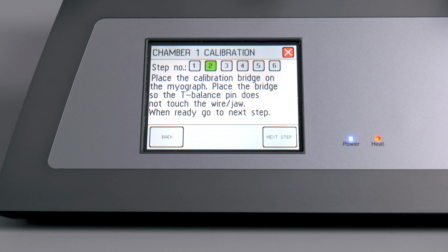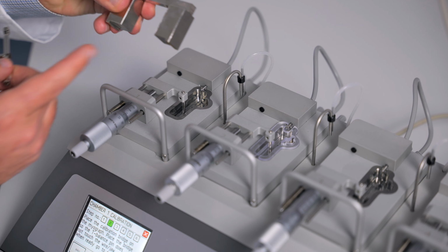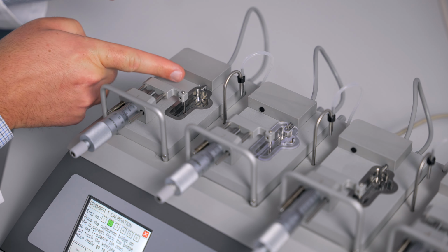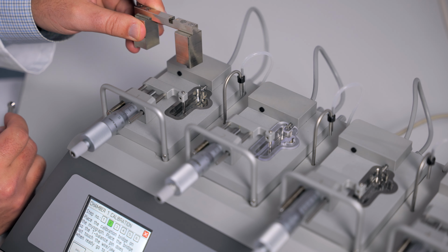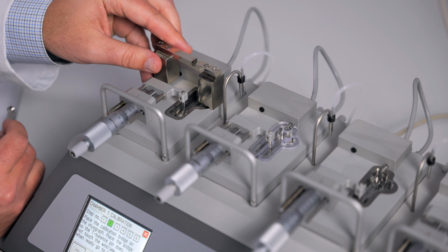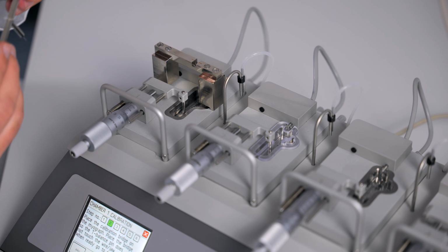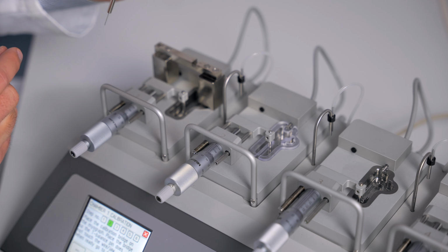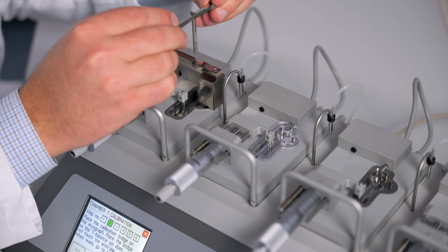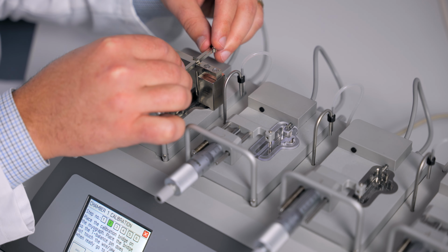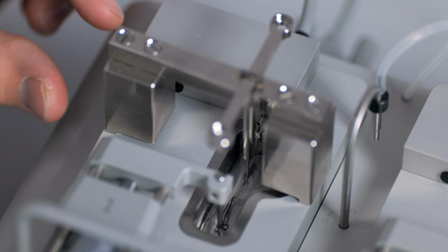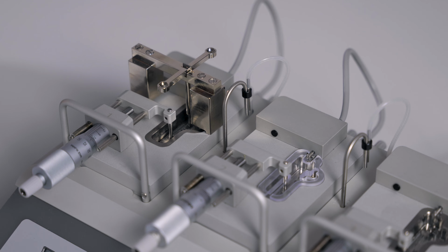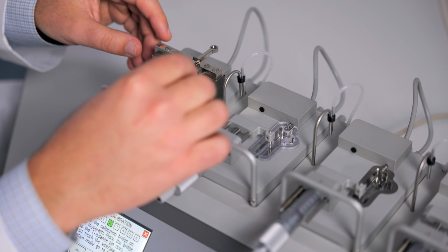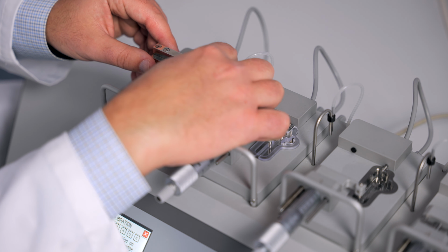Step 2 asks you to place the calibration bridge and T-balance on the myograph chamber. The calibration bridge has feet, but these feet just go above the chamber. They do not rest on the side of the chamber. So place the bridge over the chamber and place the T-balance with the small plate in the grooves on the bridge. You need to make sure that the T-balance drops in behind the pin that is closest to the force transducer. You can then move the calibration bridge until you are almost touching the back of that pin.